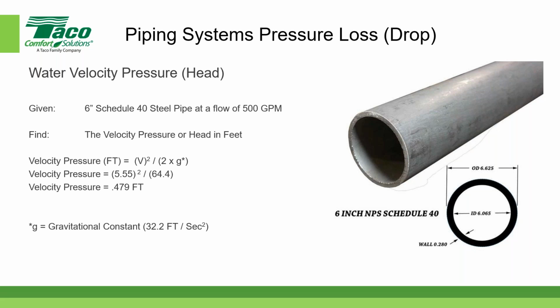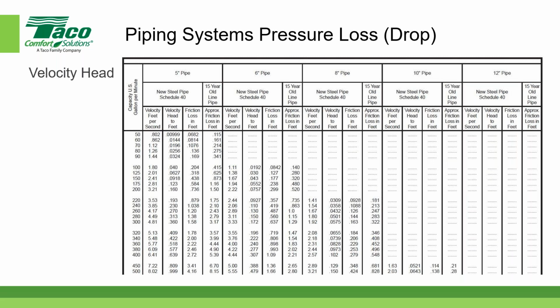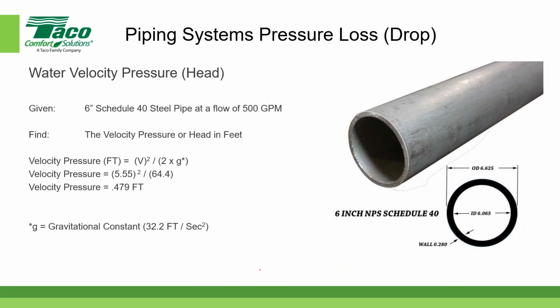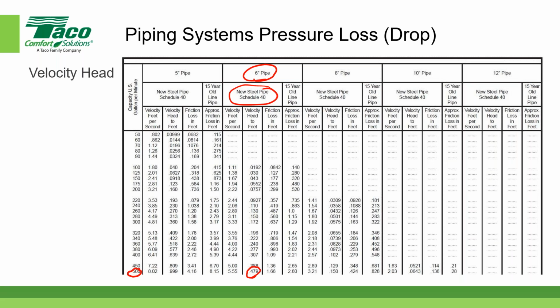And again, the asterisk is the gravitational constant of 32.2 feet per second squared. So if we go back to our table, we can see that under the column, again, this is 6-inch Schedule 40 pipe, and it's 500 gallons per minute. And you can see that the velocity head is 0.479. That's exactly what we just calculated. Let me just go back to make sure. Yeah, 0.479. Look at that. It's magic, Brett. Wow. So that's how we calculate that.